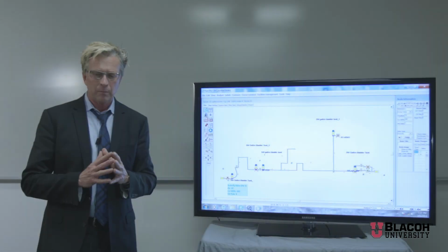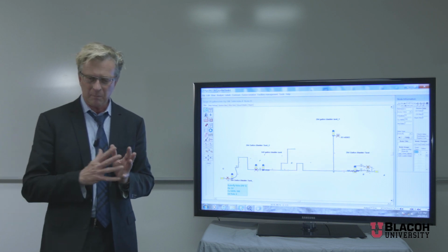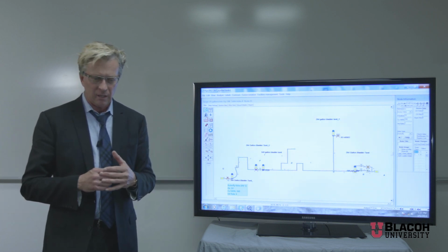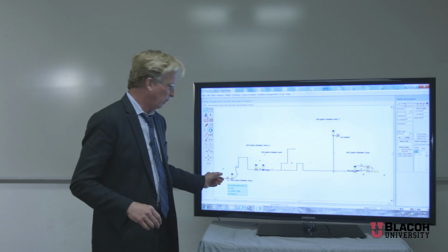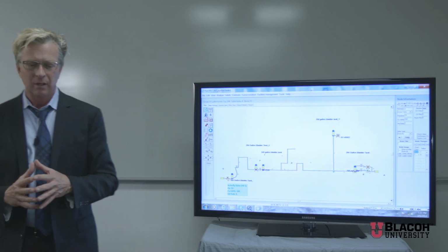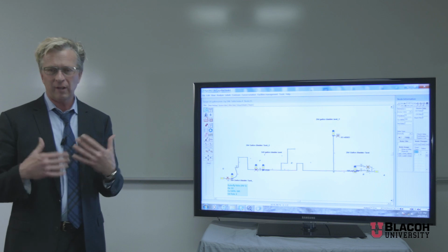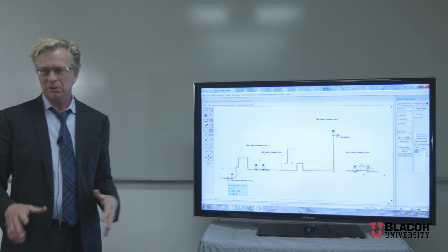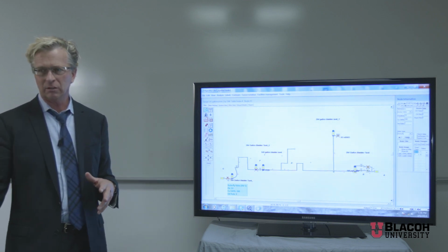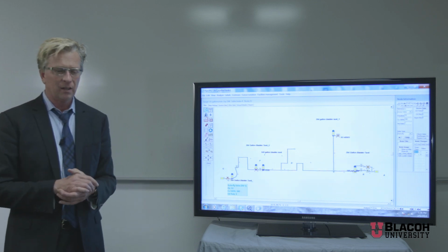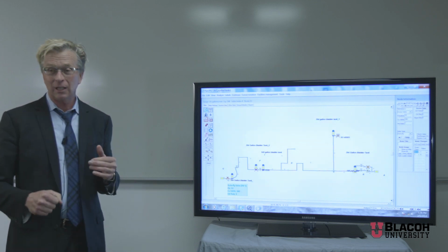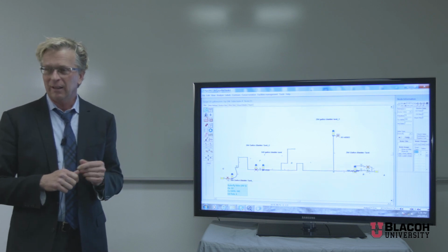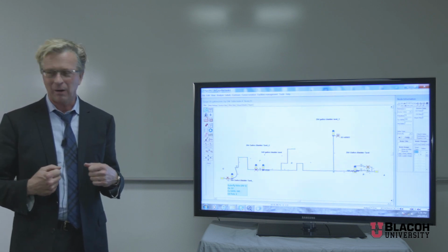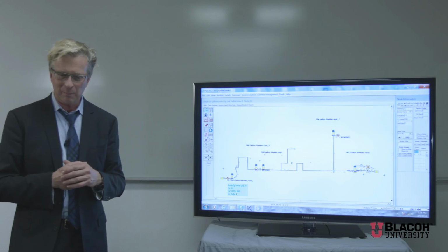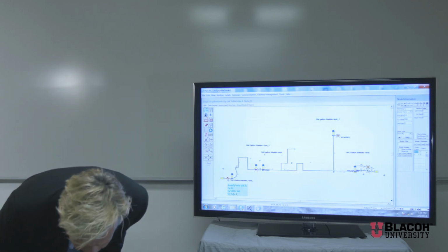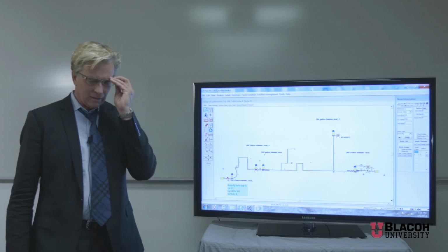We have pumps. We pump a couple miles to the river. On the river, we have a barge that we're loading, okay? Normal control valve operation, the barge is full, the control valve slowly closes off, so there's no surge event. On the barge itself, they have their own valve that the barge operator can close. So what was happening is the barge operator would close the valve in 2 seconds.